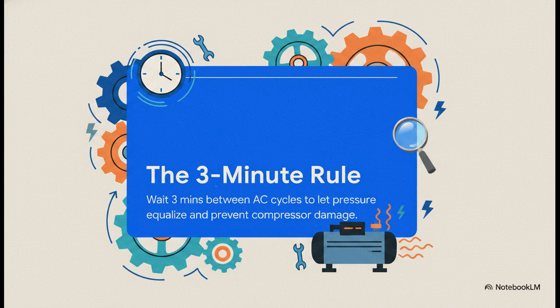Now, take a look at the 3-minute rule right here. This is so important. Your AC needs a minimum 3-minute wait between cycles to let the refrigerant pressure equalize. This vital pause protects your compressor from starting against super high pressure and overheating the motor. If a malfunctioning, oversized unit keeps cycling off and on without waiting those 3 full minutes, well, it is doing massive damage to its most expensive parts.